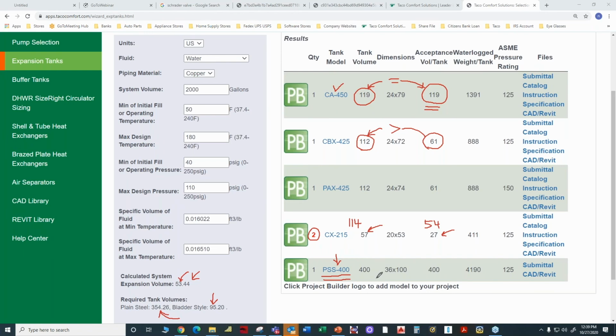And the main reason for that is you cannot pre-charge the plain steel tank. You have to start the tank at atmospheric pressure, and you have to add water to the tank until you get to the pressure that your initial fill pressure, in our case, was 40 pounds. So any questions about the selection and what partial acceptance and full acceptance, I know I'm repeating a little bit, but what all that means. Any other questions out there, Brett?